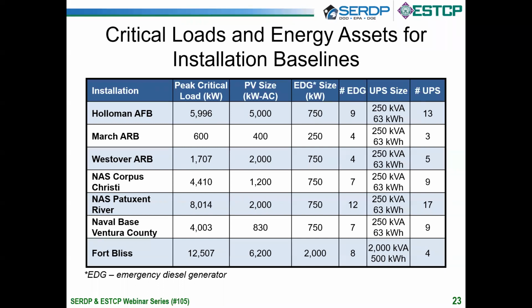The other installations, Holloman, Corpus Christi, Pax River, and Ventura County, are in the range of typical active military bases across the services. And as you can see, their peak load ranges from 4 to 8 megawatts. We also wanted to understand a variability of PV. And the key characteristic to look at the variability of PV is how much PV you have relative to your critical load. So as you can see here, the PV systems range from roughly 25% of the peak critical load to over 100% of the peak critical load. Depending on your relative PV capacity will determine how much energy you can store in your battery system and how much that will contribute to a resilient energy solution.